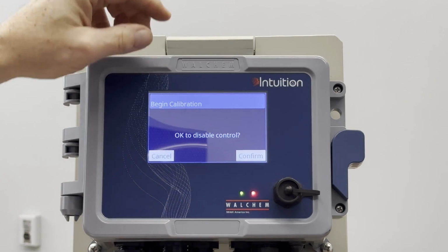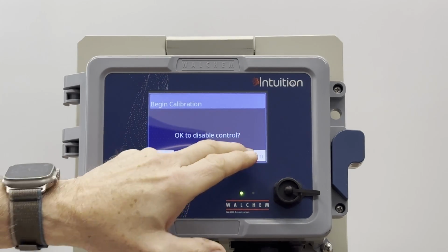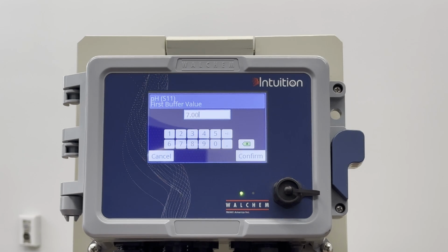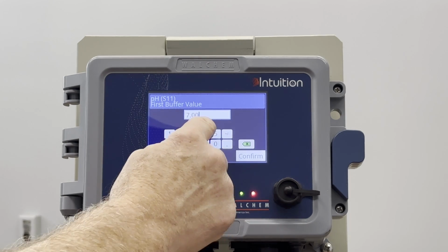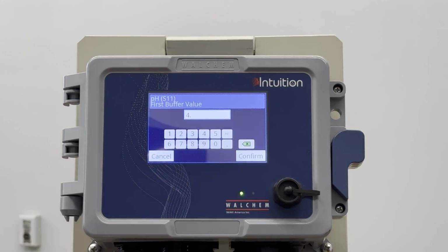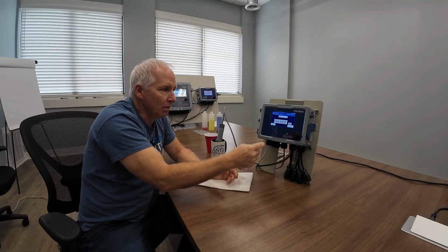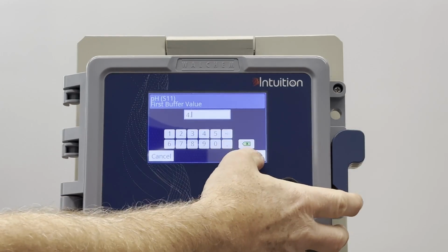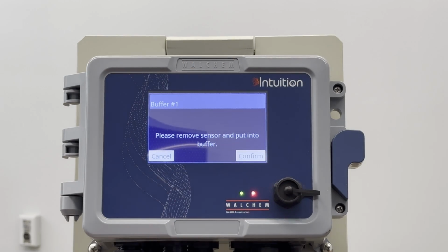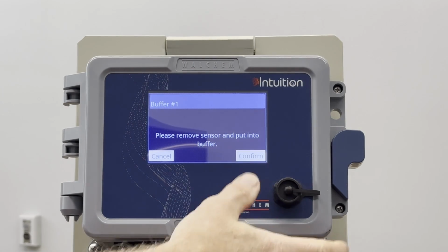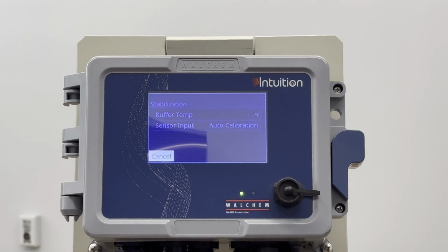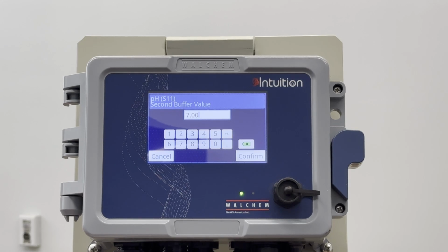It asks if we want to disable control, which we've already done, but we say yes, go ahead. And it'll ask what buffer we are using first. We've already let this stabilize in 4, so I'm putting in the value of 4 and hitting confirm. It tells me to go ahead and put it in there. We've already done that, so I can confirm, and now I wait for it to stabilize. It does its own stabilization, and then it tells me to continue whenever it thinks everything's all right. Now it's telling me to go to the second buffer.